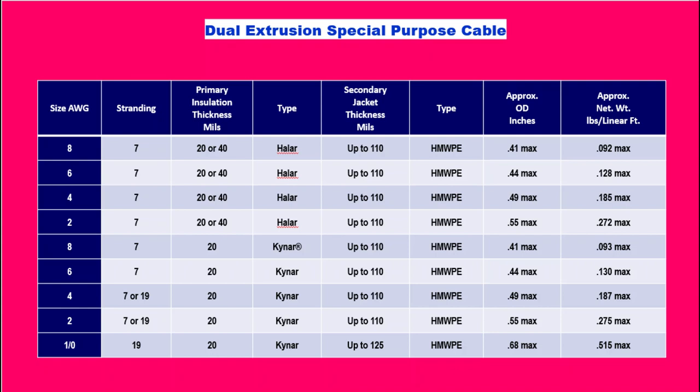For dual extrusion special purpose cable, specifications include size in AWG, stranding, primary insulation thickness in mils and type, secondary jacket thickness in mils and type, approximate OD in inches, and approximate net weight in pounds per linear foot. For example, 8 AWG with 7 stranding, 20–40 mils primary insulation (halar type), up to 110 mils secondary jacket (high molecular weight polyethylene), has a maximum 0.41 inch OD and 0.092 maximum lbs/linear foot. A 1/0 AWG with 19 stranding, 20 mils KYNAR primary insulation, and up to 125 mils high molecular weight polyethylene secondary jacket has a maximum 0.68 inch OD and 0.515 maximum lbs/linear foot.